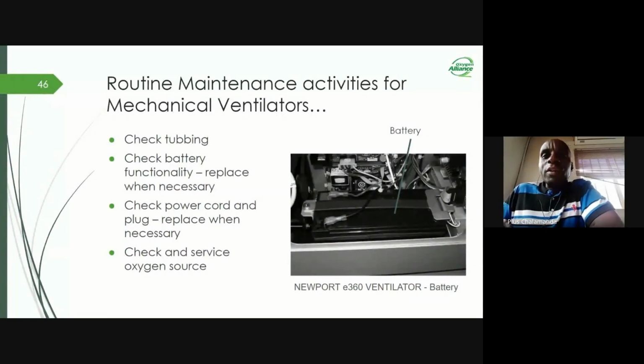Check the battery functionality, replace when necessary. Check the power cord and plug, replace when necessary, and also check and service the oxygen source. Whatever the oxygen source, it might be an oxygen concentrator, oxygen cylinder, or the gas plant. They all need service at one point or the other.